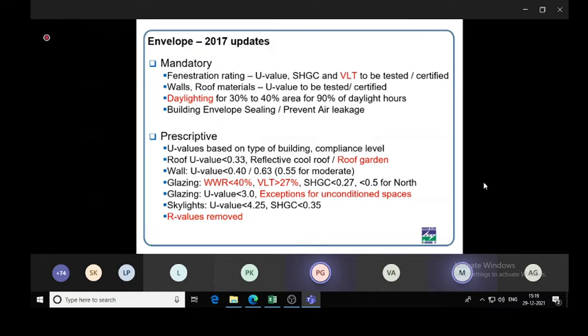All right. Okay. So actually, glazing design is a separate subject in itself. From the ECBC point of view, or from a general point of view, generally the glazing towards the radiation should be minimized. For example, east and west, ideally should have the minimum amount of glazing, and north and south, it's better to have the maximum amount of glazing because the direct solar radiation is not there. The objective of glazing is mainly to have daylight and views. So when you give it on north and south facades, the direct radiation is not so much. Therefore you get a lesser amount of heat and a good amount of daylight. That is the idea.